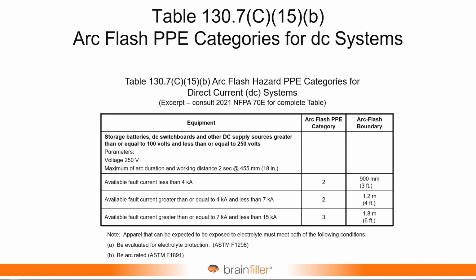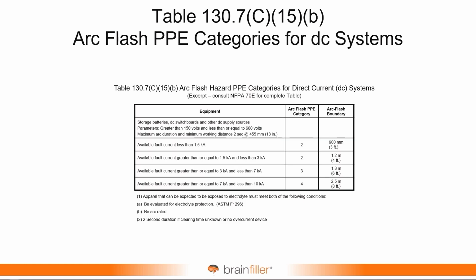This was the table that we had, the table that was 100 volts to 250 volts. This was removed, and now we just have the table that has been repurposed for voltages greater than 150 volts up to 600 volts. And we have the 4 different categories here. Down at the bottom, it should be noted, there's a 2-second duration referenced. That comes from IEEE 1584. IEEE 1584 suggests if you have a long duration, an unusually long duration, or no protection at all, if there's room to escape, it may be reasonable to assume that the person will be gone within 2 seconds.